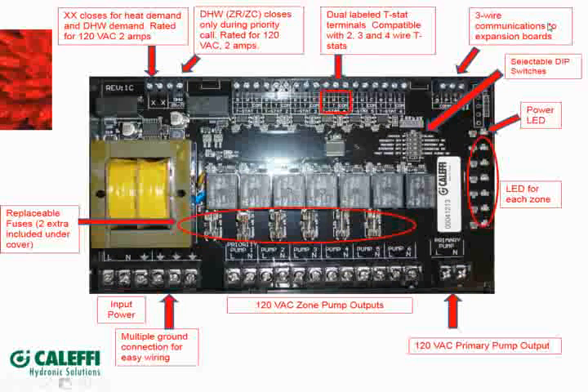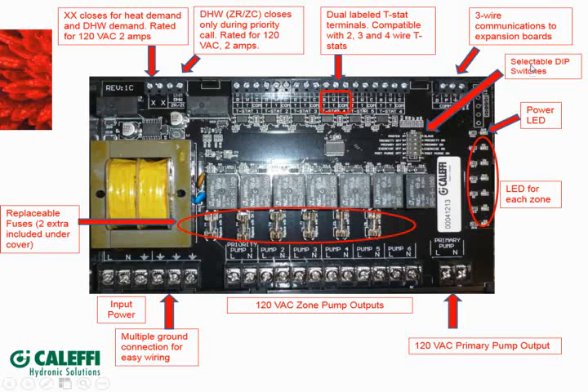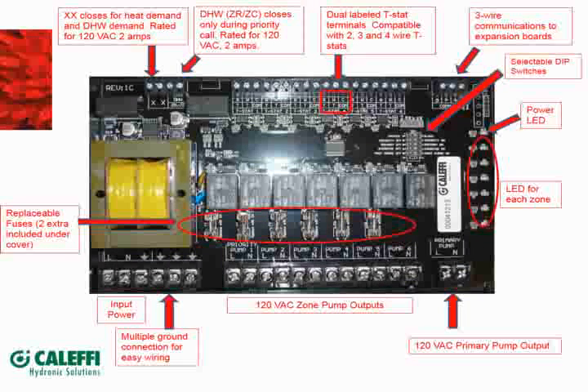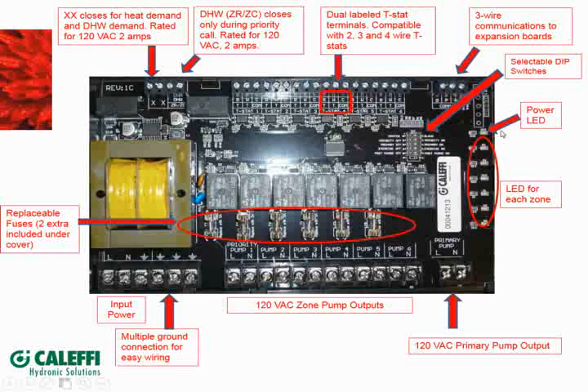We talked about that. Now here's where the communications occurs. It's a 3-wire communications to all of the boards. There's a D, a P, and a ground. It will communicate from the boards whether there's a demand or whether there's a priority call on the other boards, and control the pumps and valves accordingly. There's a power LED. On the communication, Mike, a second, let me interrupt. What's the wire that's needed to connect them to communicate? Just a bell wire. It's a 5-volt control signal going between those. Yeah, so it doesn't have to be a line voltage wire for the 120 volt. It's just communicating through thermostat wires, shielded wires. Yeah, that's all low voltage.